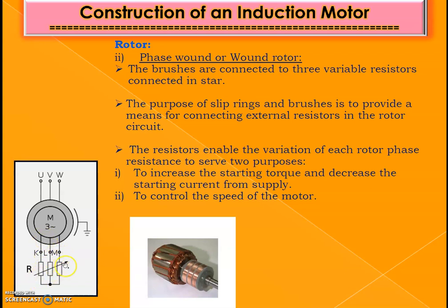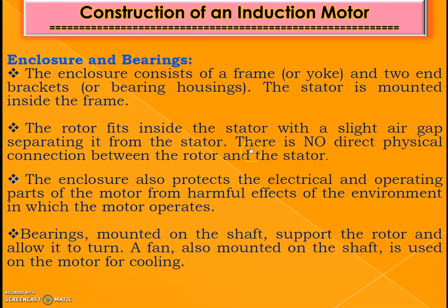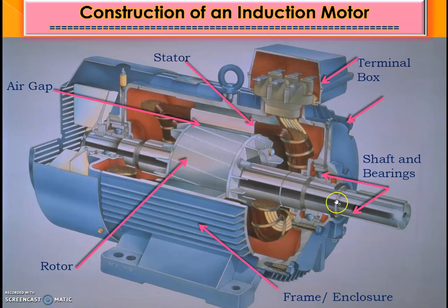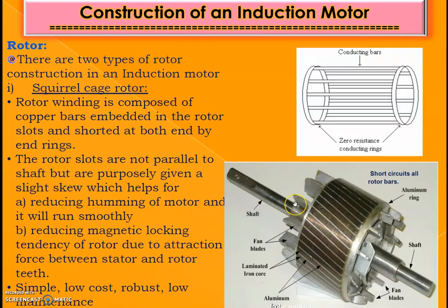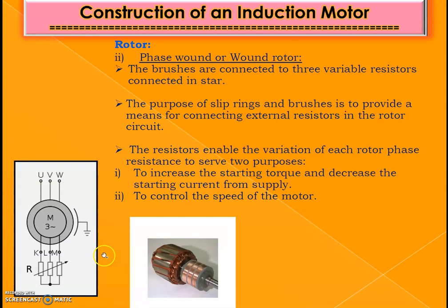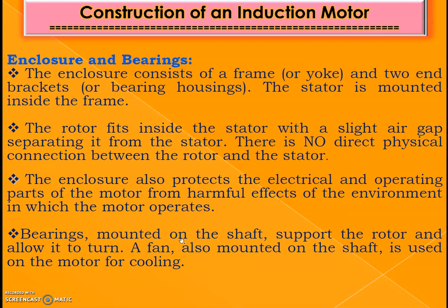The rotor winding can be shorted externally through external resistance or shorted directly. Each slip ring carries a carbon brush and can be connected to external resistance. This increases the starting torque, decreases the starting current, and controls the speed of the machine — it is generally used for high-rated machines. Enclosures and bearings are used to fit the stator and rotor, creating an air gap between them. Bearings are mounted on the shaft to support the rotor, and a fan mounted on the shaft provides cooling by passing air through the machine.